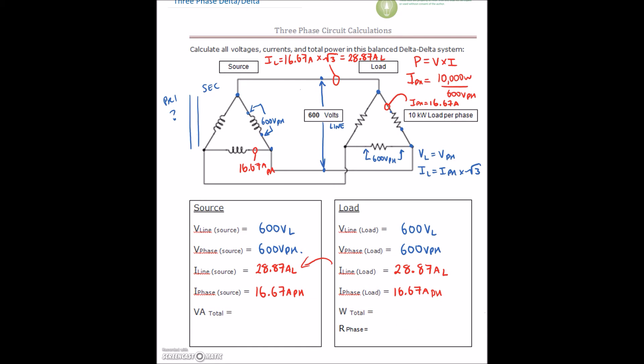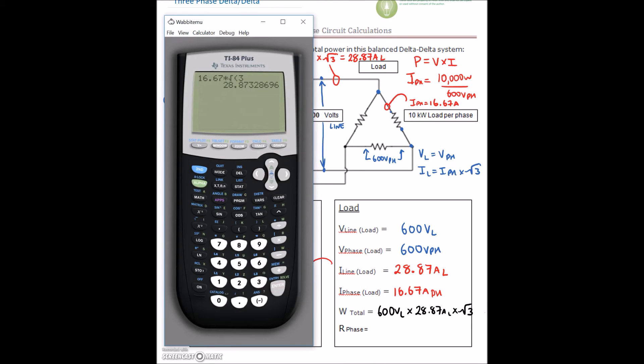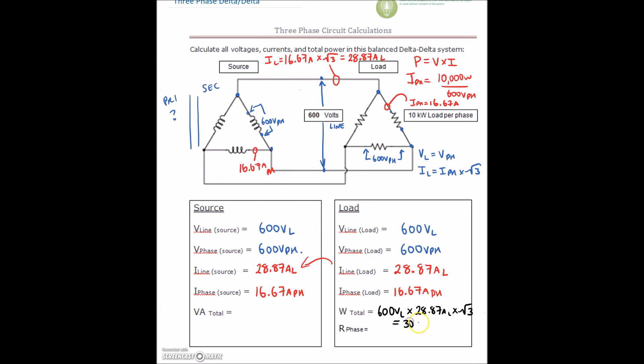For the line values, we're going to do V line — 600 volts on the line — times our total current on the line, 28.87 amps. Because we're using line values, we multiply by root 3. That gives us 30,000 watts. So this is 30 kilowatts. That makes sense: if we take a step back, we had 10,000 watts on the phase — 10,000 here, 10,000 here, and 10,000 here — so the total is 30 kilowatts.